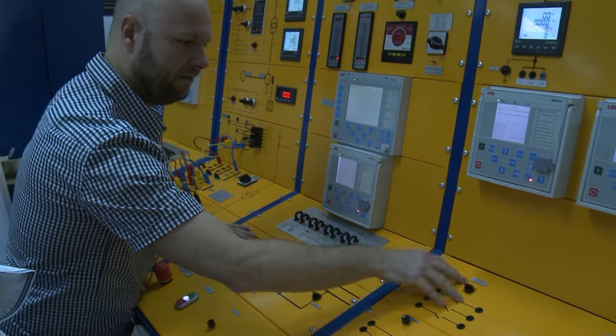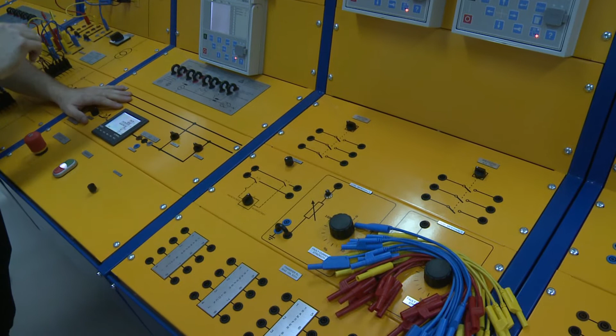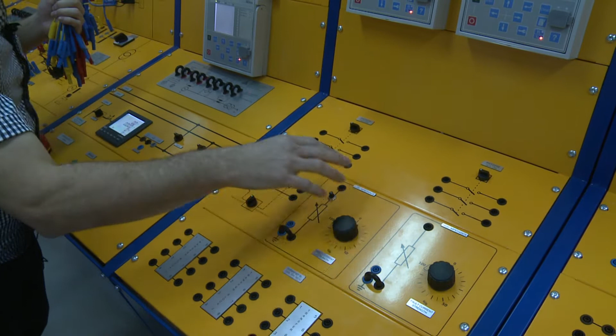Next panels, here we have a couple of contactors we can use. These we can use from SCADA as well. This one we'll demonstrate when we're connecting faults and things, if we want to connect them remotely. The next panel here is our fault simulation panel. This allows us to connect faults in a safe way. We have two different impedances. This one will allow quite large current, and this one will allow less current. We can make earth faults. We can make phase-to-phase faults and things like that through this.